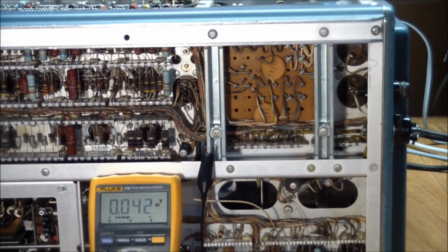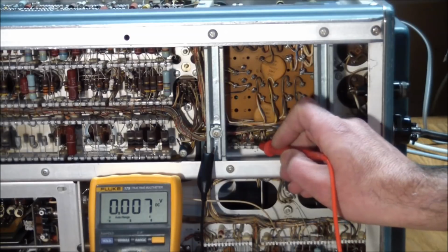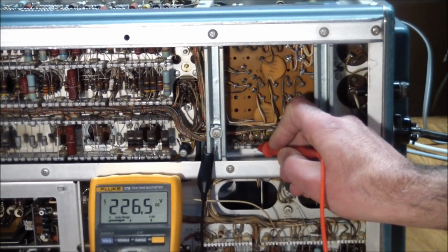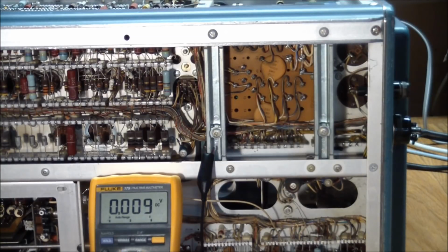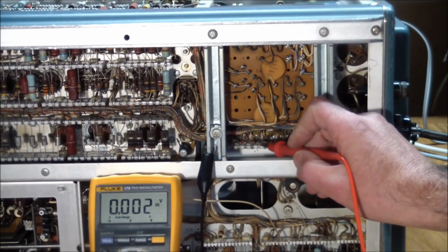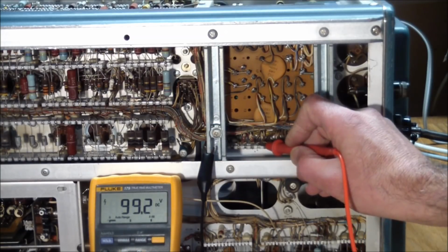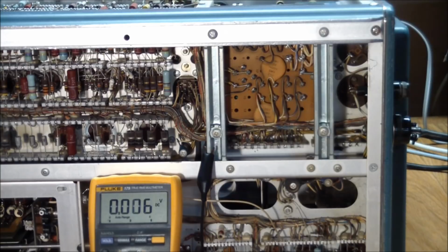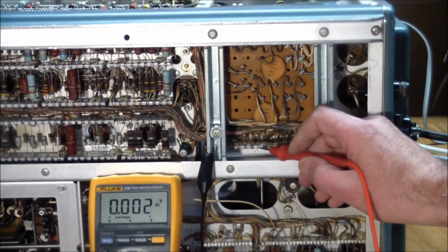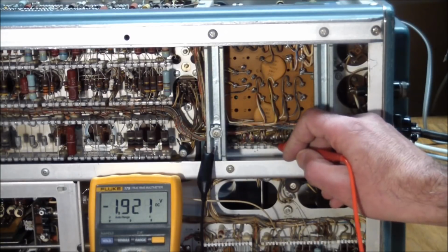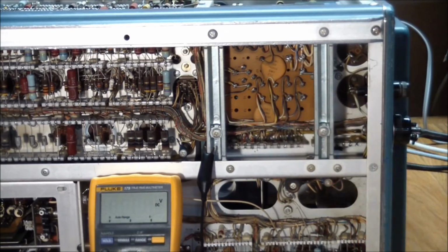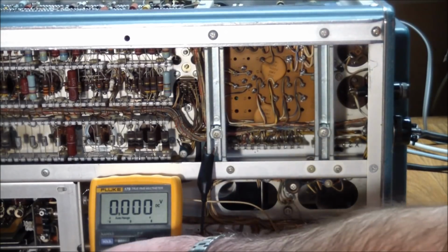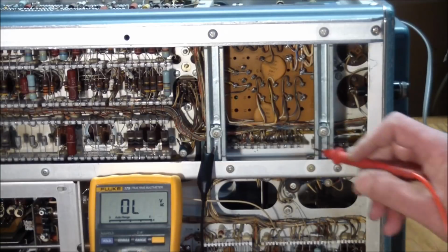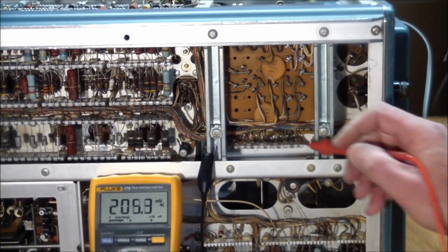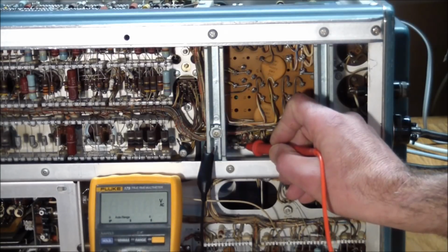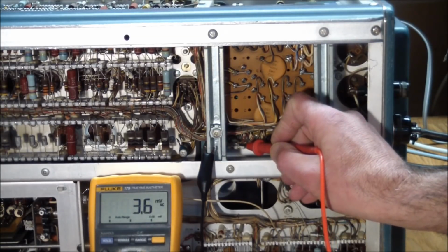and they're pretty close. The second pair should be 225 volts. That's also good. The third pair of contacts should be 100 volts, less than 1% off. And the fourth pair of contacts is minus 150 volts. So it looks like all the DC voltages are right on. Let's check for ripple now, starting with the 350 volt supply. Well within spec.